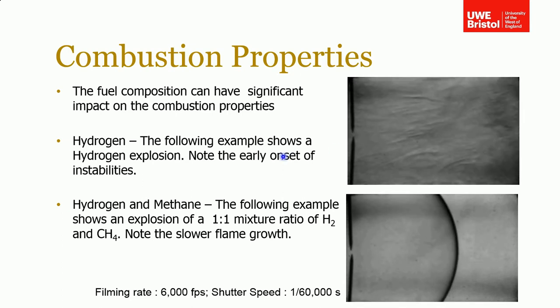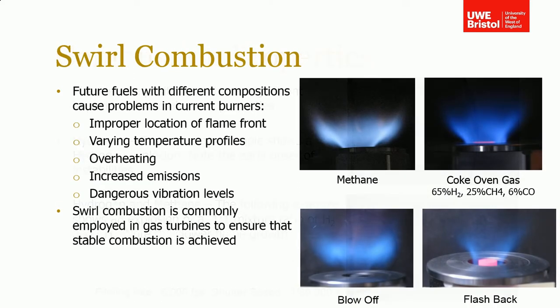What impact does that have for a gas turbine designer? Quite a lot, because the future fuels we're looking at — some from anaerobic digestion and different sources — can have quite large quantities of hydrogen in them. Changing the hydrogen composition in the fuel can change the flame speed dramatically. If you've designed your combustor to run on just methane and then suddenly you've doubled the flame speed, you can have improper location of the flame front, different temperature profiles, overheating, and increased vibration levels.